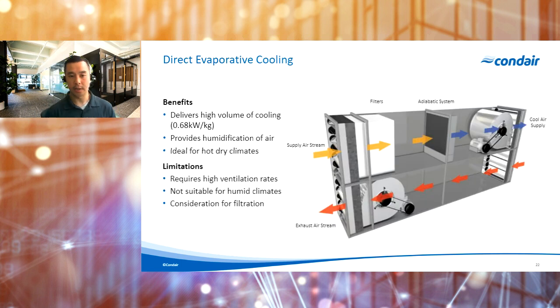So both of those technologies that we just looked at are commonly applied in what we call a direct evaporative system. So in this case, the adiabatic system is placed directly in the supply air stream, and we are cooling and humidifying that air that is supplied directly to the space. So this type of configuration is really ideal for hot, dry climates where the air can hold more moisture and allows for the highest amounts of cooling. With this system, however, it does typically require higher ventilation rates in order to maintain that cooling capacity. So it's not really suitable for humid climates where evaporation is limited as well.